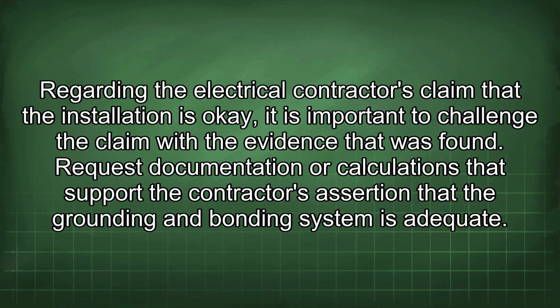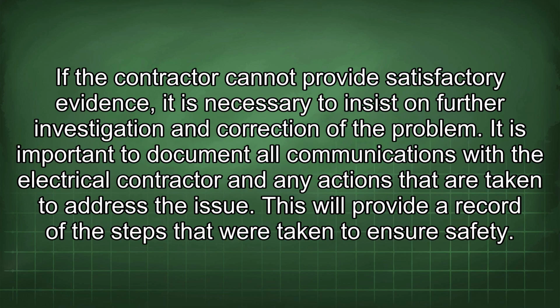Regarding the electrical contractor's claim that the installation is okay, it is important to challenge the claim with the evidence that was found. Request documentation or calculations that support the contractor's assertion that the grounding and bonding system is adequate. If the contractor cannot provide satisfactory evidence, it is necessary to insist on further investigation and correction of the problem. It is important to document all communications with the electrical contractor and any actions that are taken to address the issue. This will provide a record of the steps that were taken to ensure safety.